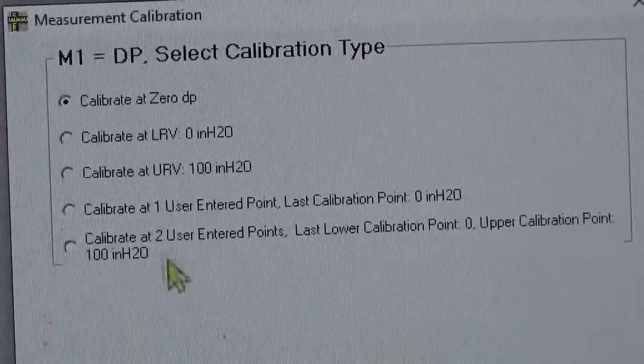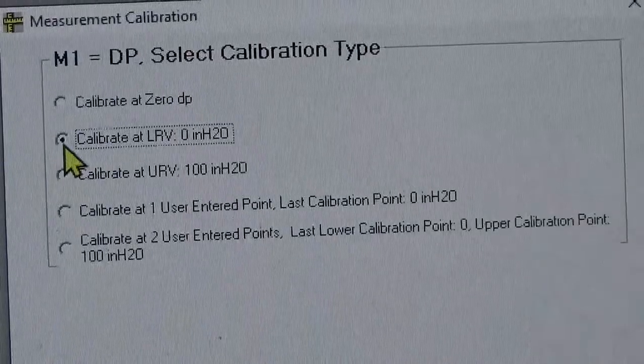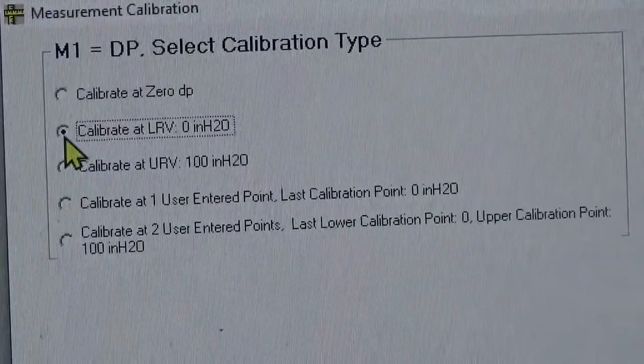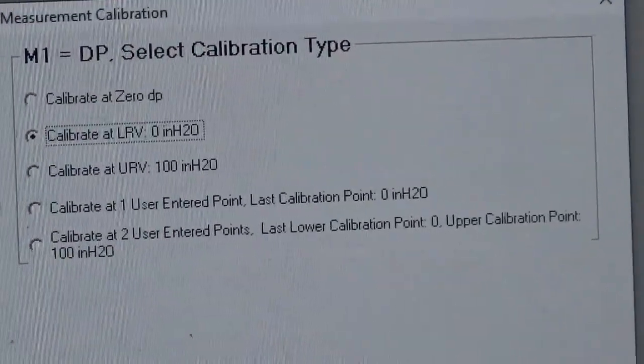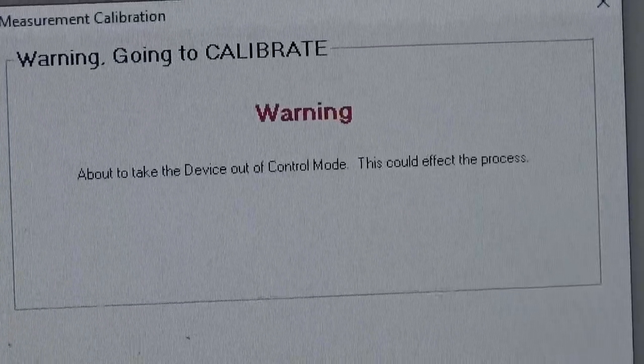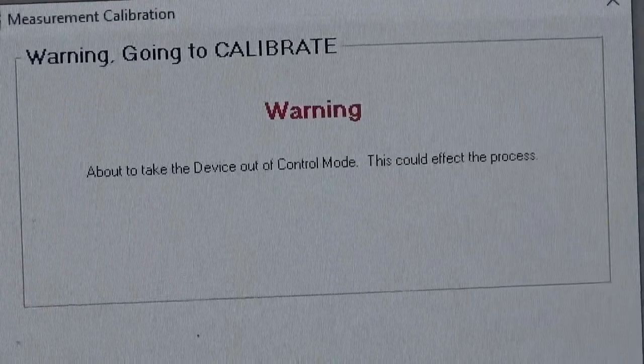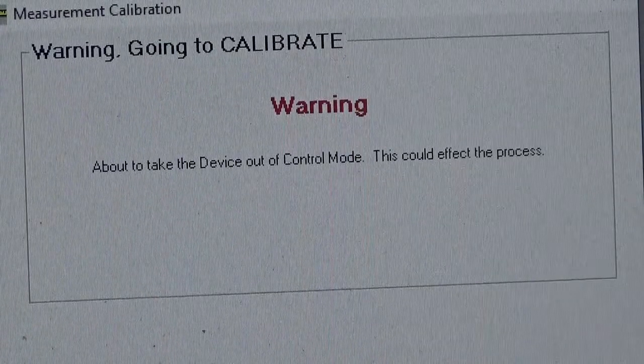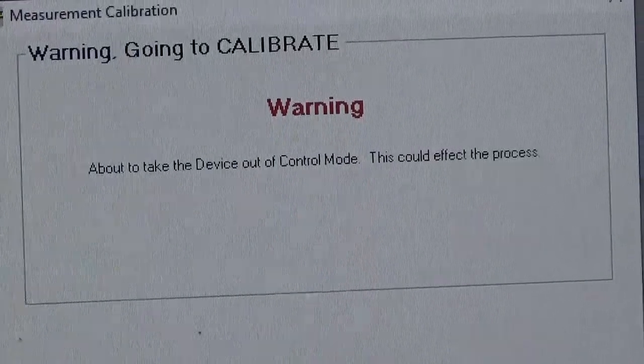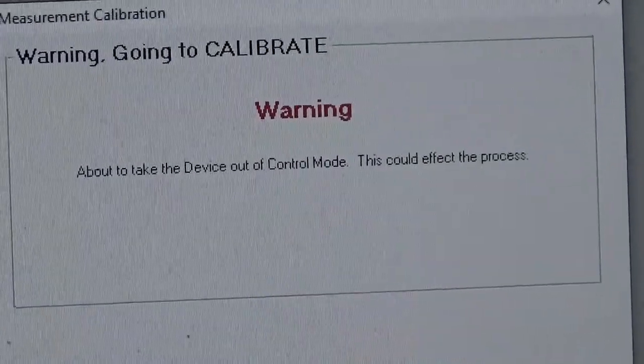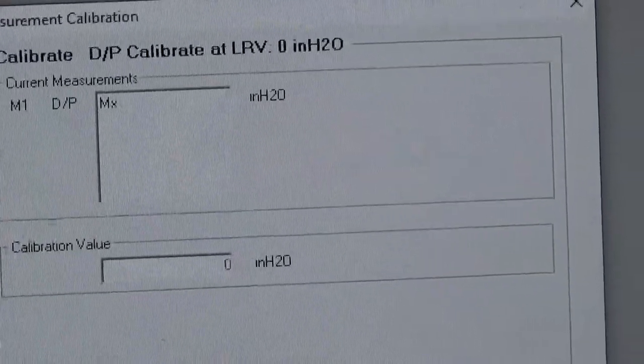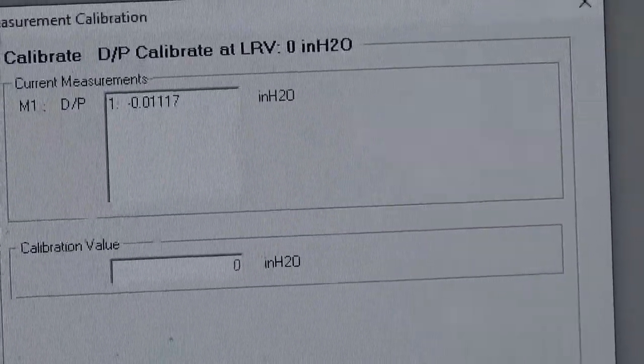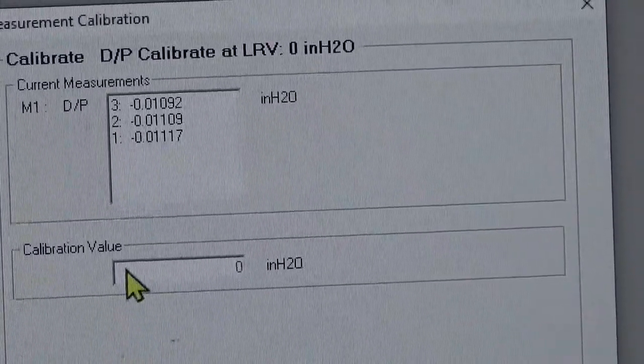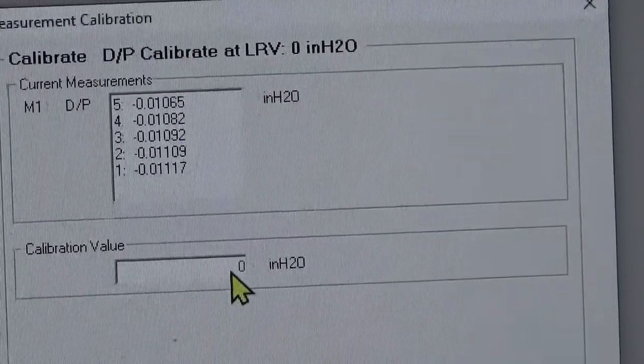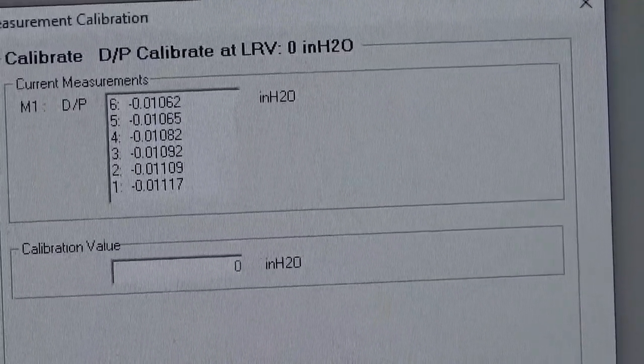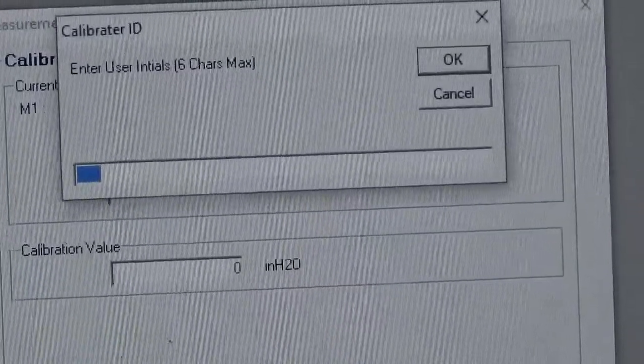So I'm first going to select 0 differential, which is being applied to the transmitter right now. There's no pressure on it. Click the next button. I'm going to get a warning telling me that the device is going to go out of service and that it will not be able to control anything. Click next, and it's going to show me the calibration value that needs to be entered. And I'm going to click calibrate.